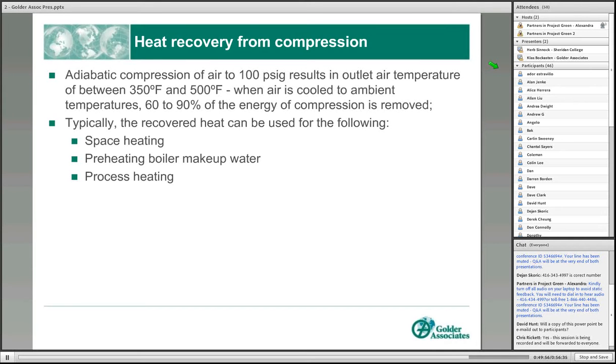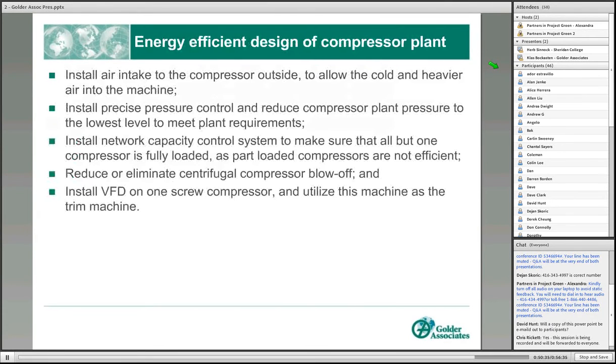You could use it for preheating boiler makeup water if you have a steam system in the plant. It could be used for process heating, heating process vessels, etc. And if the compressed air system is air-cooled rather than water-cooled, you could set up a duct system to direct the waste heat from the air cooler into the plant for space heating in the winter. In the summer, of course, you don't need it, so you'd have to discharge it outdoors. But the benefit of a process heating load is that it will typically be year-round, so you could use that waste heat year-round as a cost-effective way of generating process heat.